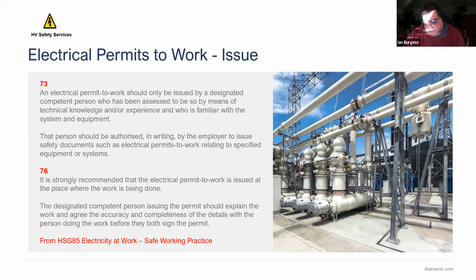I'd take that a stage further. I'd like to see, when I issue a permit, that I issue it to the recipient, who then explains it back to me so I can check understanding, and make sure that they have got what I want done, and they know where the work is, they know where the safety areas are, they know where the potential energized equipment is. And then I like them to issue that document to their teams. And then I get another check that they're explaining it out to everybody that is working in the area.